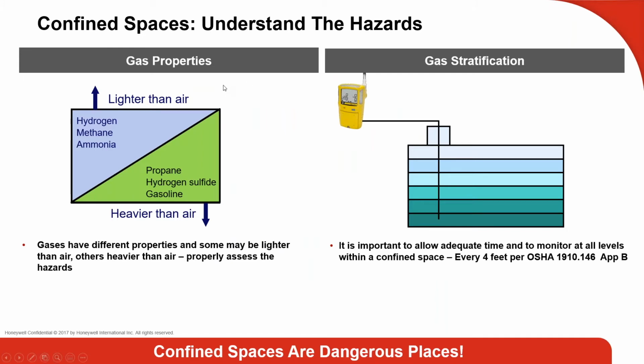And just understanding the hazards, like we said, some gases are lighter than air, both combustible and toxic gases, as well as gases that are heavier than air. So what you see on the right-hand side is a rule of thumb to go every 4 feet in the direction of travel. If you had a 10-foot drop, typically it would be top, middle, and bottom, and you would want to detect for the gas for a significant amount of time. Give the time that it takes for the gas to come up the hose, and also additional time for the sensors to reach what's called T90 response time. That's the time it takes for the sensors to reach 90% of full response. Often you can get there within 30 seconds, whereas if you want the full 100% response, you may have to wait a minute to a minute and a half longer.